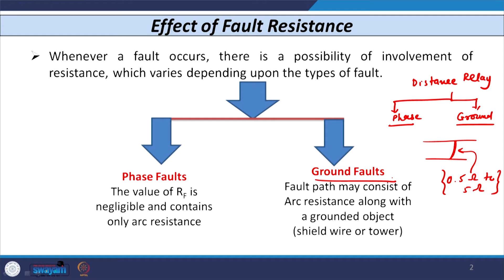So, whenever a ground fault occurs, the value of fault resistance is very significant, we cannot neglect it, as we have neglected it in case of phase fault. So, the arc resistance changes with reference to time as the fault current continues to flow. If I consider that the fault occurs from this instant, the magnitude of current becomes very high. From this instant, if you take one cycle or 1.5 cycles, then the value of arc resistance is very small, and as the fault current continues, its value also changes.